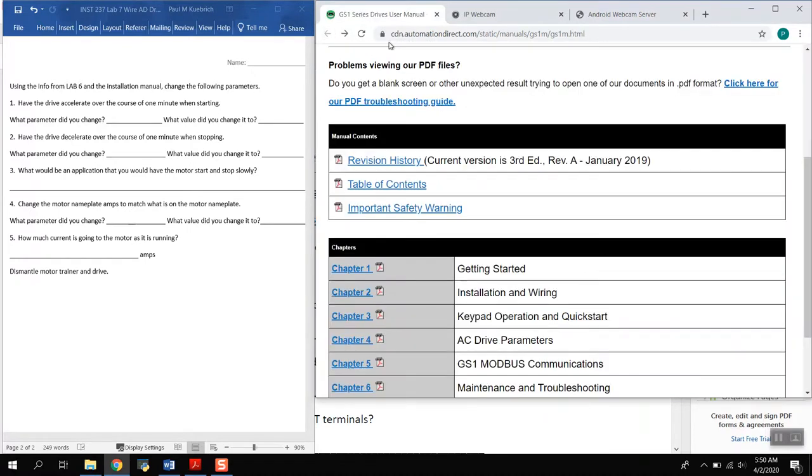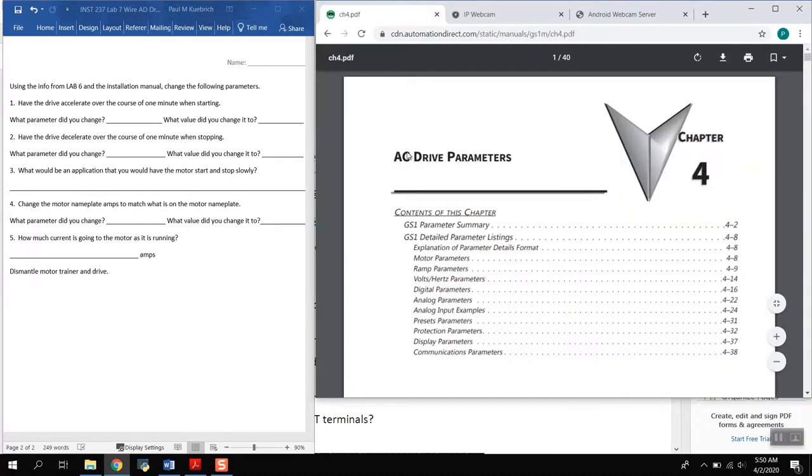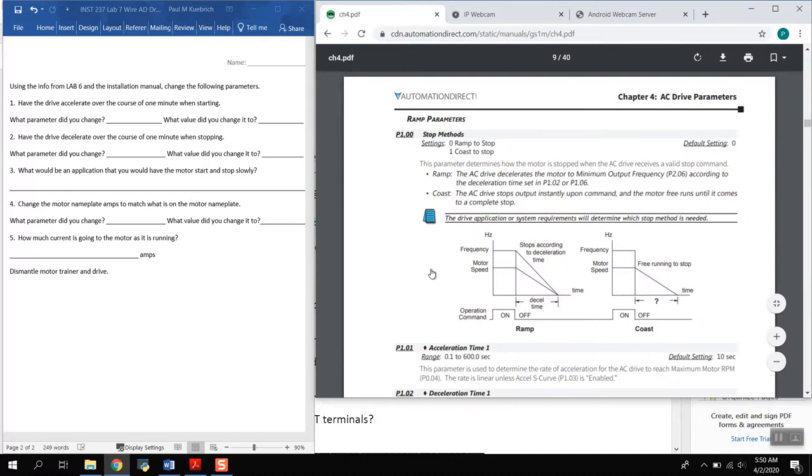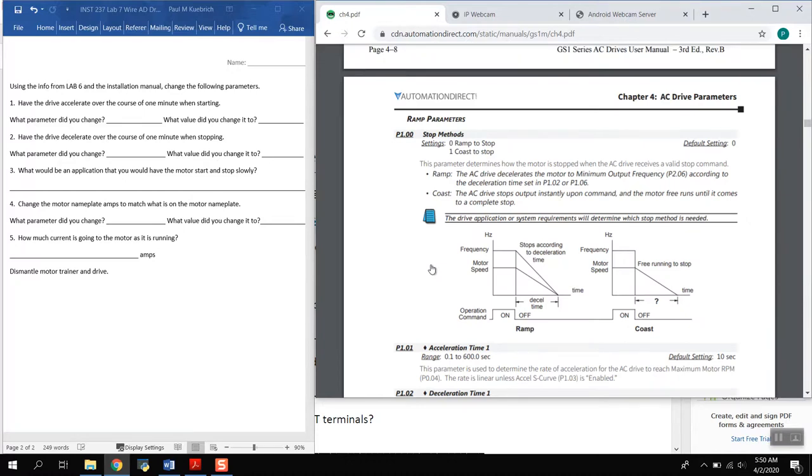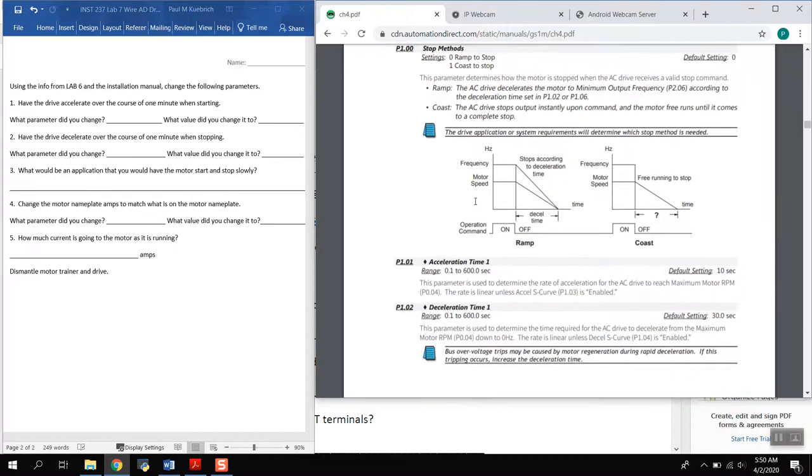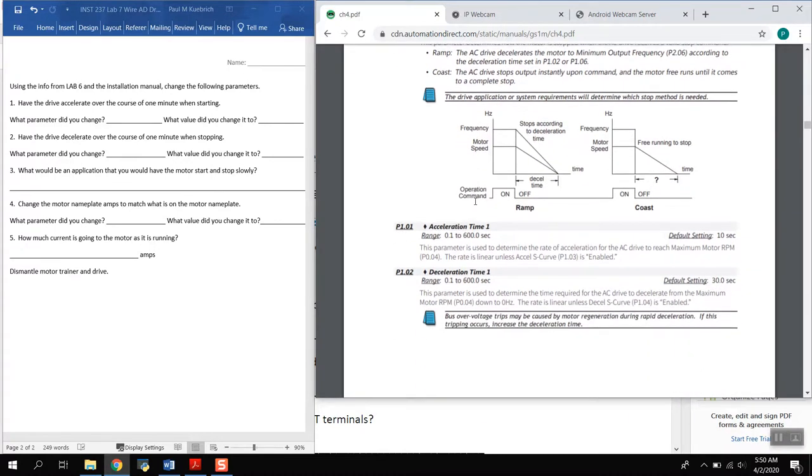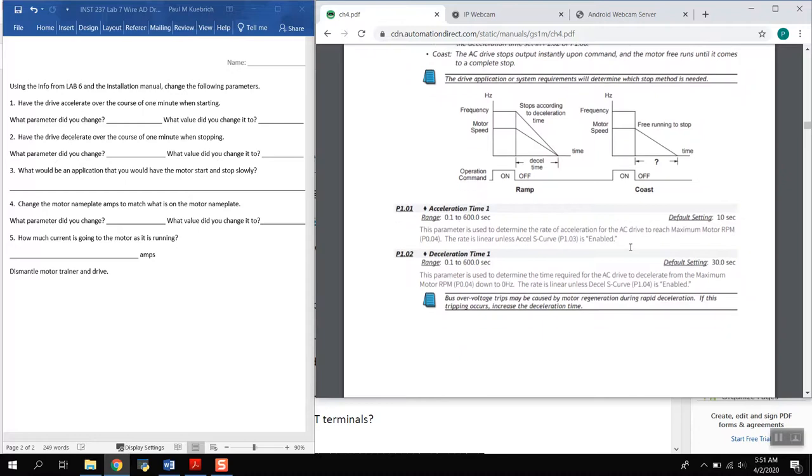This is just the user manual, you just jump right down to drive parameters and we jump right into ramp parameters. That's what we're talking about, ramp, and we want to accelerate or decelerate over a particular amount of time. So what we're going to do is we're going to look for the acceleration time range from anywhere from 0.1 to 600 seconds. The default setting is 10 seconds.